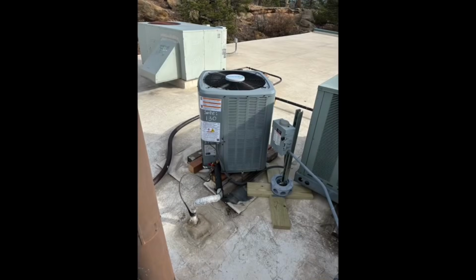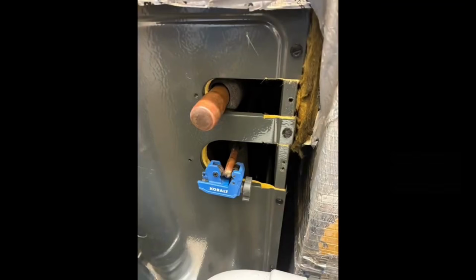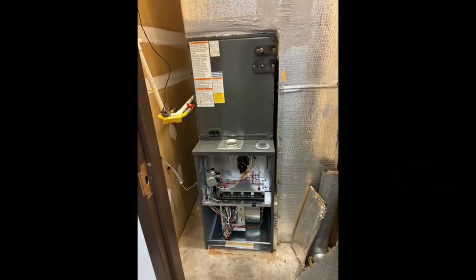We will not release the refrigerant yet because we still got to do a nitrogen test and then do a decay test with our vacuum pump. Let's go downstairs here on the evaporator. We need to cut this loose. When you cut it loose, you should hear a purging noise of the nitrogen that's inside the unit. That's normal, comes from the factory that way.